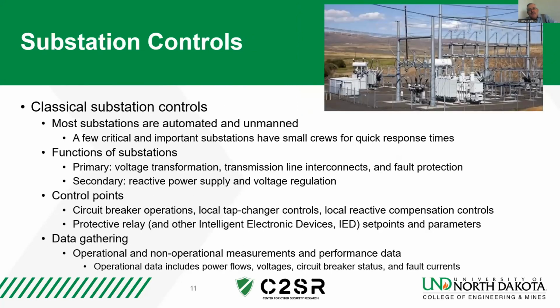Substation controls. Most substations now become automated and unmanned. There are a few that do have humans nearby at very critical substations. Remembering that our primary functions of substation is voltage maintaining, distributing voltage levels to the various parts of the system, providing fault protection. Control points are transformers, tap changers, voltage regulator controls, operating of auxiliary equipment like the capacitor bank sections, operating those switches. The intelligent electronic devices and the protective relays are responsible for carrying out these operations. A number of PLCs are found in this area to automate sequential operations of events.